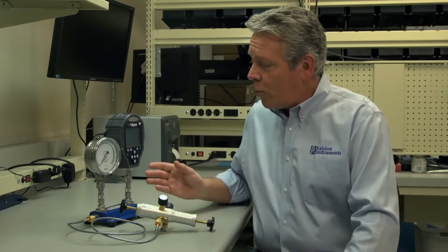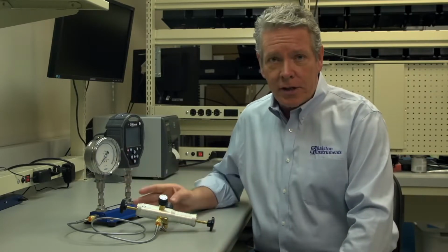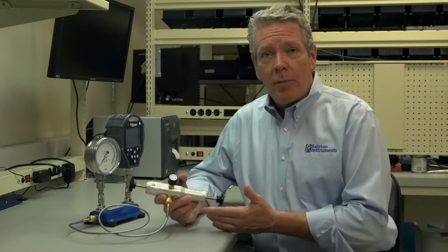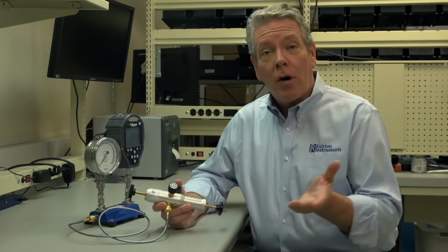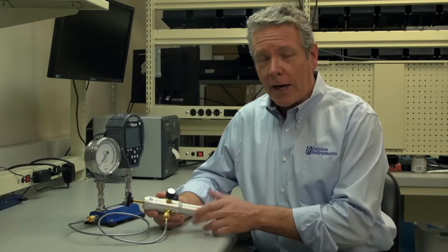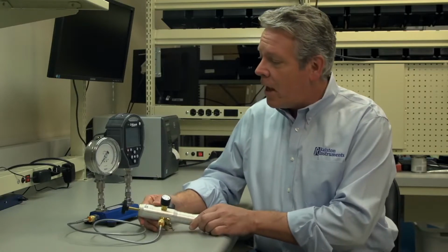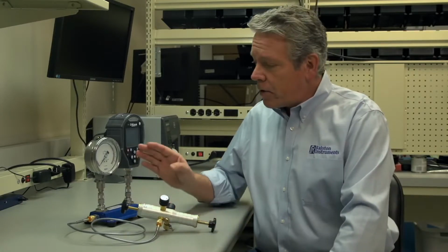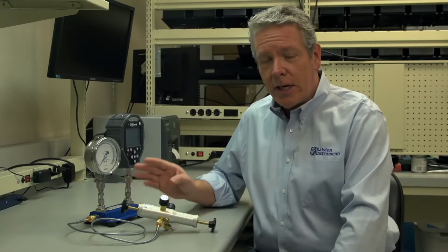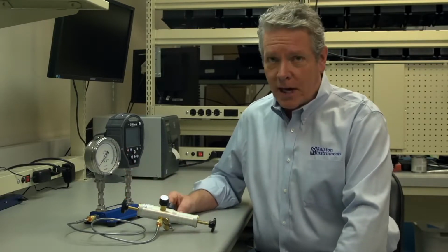You'll have your FieldLab reference and your DUT connected to the same pressure supply. Of course, we recommend a Ralston pneumatic hand pump or our hydraulic hand pump or nitro pack for higher pressure devices. Now I'll demonstrate a calibration test of this 1/4% full-scale accuracy 30 psi analog gauge.